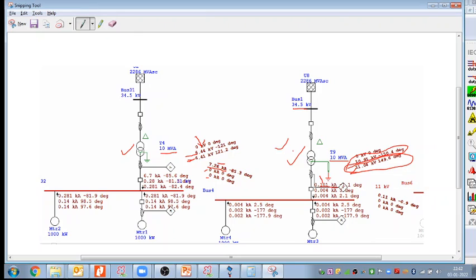Excuse me, sir. I have a clarification. This is with regard to where the NGR is supposed to be used. You said that mostly it will be used in places where you have rotating machines, due to the concern for the core. Why is it not a concern for the transformer also? Because the transformer also has a core, and it may also get damaged if you don't use the NGR.